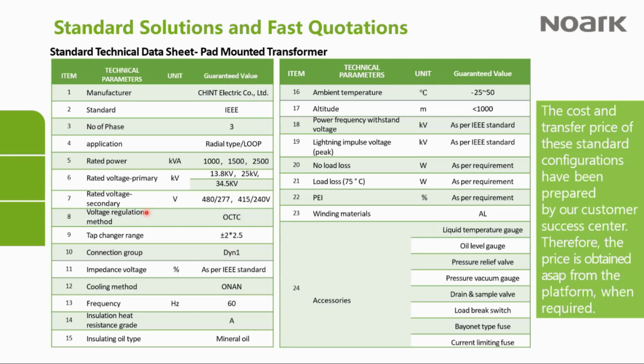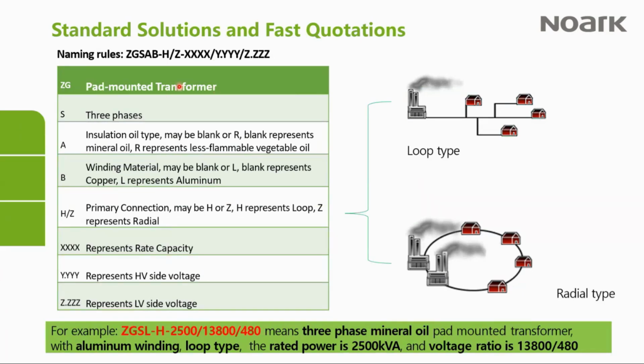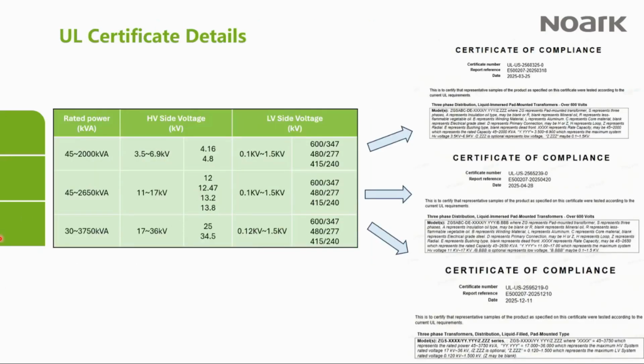Thank you. This is our spec sheet that tells you a lot more about what we are doing in terms of the spec for the transformer. I won't go into a lot of details here, but it summarizes what our spec sheet looks like for a standard transformer. And in terms of the product naming, this slide is just explaining what we mean when we say you need a 25 kVA transformer, and on the primary side you need 13.8 kV, and on the secondary you need 480 volts. This shows you what each of those numbers stands for. I won't go into a lot of details there, because in our catalog you have all this information, and you can avail yourself of it later on.